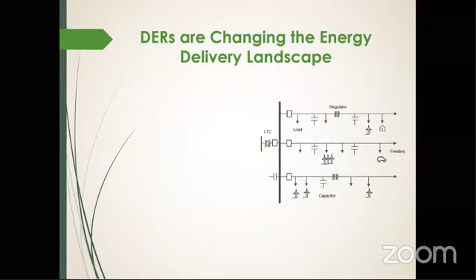Do we need increased short circuit interrupting capability by protective devices because of DERs? More importantly, do we need to adaptively change the settings and coordination of protective equipment because of changing conditions in the grid? Then there are faults dropping out, inverters covering hidden load.